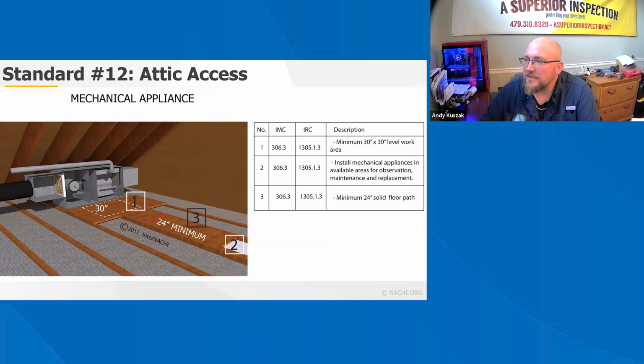A light fixture should be installed to illuminate the passageway of the mechanical appliance. A control switch should be installed near the entryway to the passageway. An electrical receptacle should be installed at or near the mechanical appliance to allow for safe and convenient maintenance and service of the appliance. And the rough framed opening to the attic area should be at least 30 inches by 22 inches. If the opening to the attic area is installed in a ceiling, there should be at least 30 inches of vertical headroom in the attic space measured above the access.